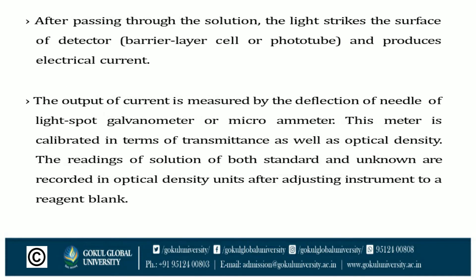After passing through the solution, light strikes the detector surface — a barrier layer cell or photo tube — and produces electrical current. The output current is measured by deflection of a galvanometer or microammeter needle. This meter is calibrated in terms of transmittance and optical density. Readings of standard and unknown solutions are recorded in optical density units after adjusting the instrument to a reagent blank.